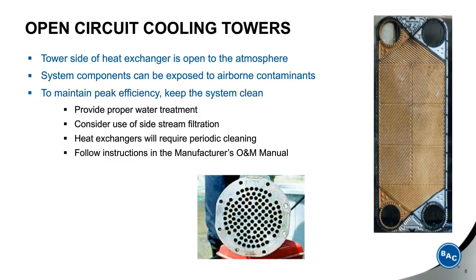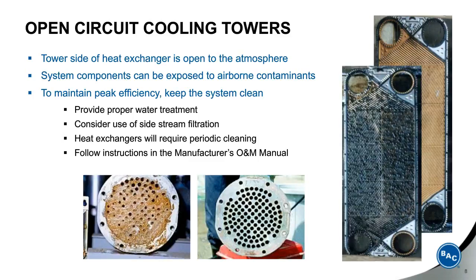Now, heat exchangers will require periodic cleaning. You can see here the difference between a clean plate and frame heat exchanger plate and one that's been fouled, as well as a shell and tube heat exchanger that is fouled. So you need to make sure these are cleaned when you see the performance starting to degrade in the heat exchangers. So be sure to follow instructions in the manufacturer's operation and maintenance manuals for all your equipment in the system.